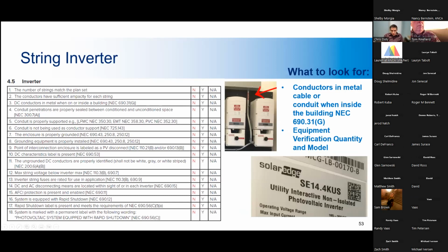All right, so next we'll go through some string inverters. This section of the checklist asks for equipment verification. It's vital to ensure that the actual installation matches the design submitted in the permit package construction documents. Conductor sizing is based on the information provided by the manufacturer. If a contractor substitutes the inverter model, it can be oversized for the conductors carrying the output current. Like I said earlier, if the current is too much for the wire, it can cause the wire to melt and create fire hazards. So it's very important to make sure that the conductors used are rated for the amperage that they carry.